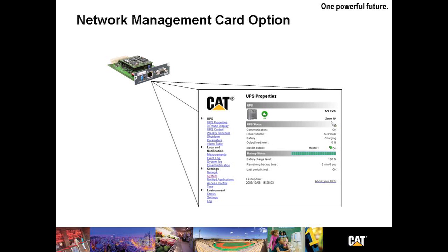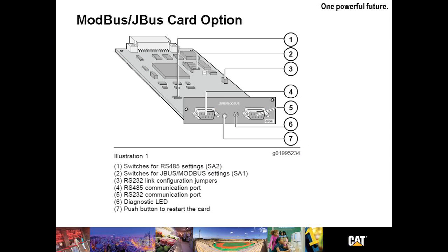The network communication card allows the user to directly connect the UPS to a computer network. The card simultaneously operates as a web server and an SNMP agent. Remote connections are made using an ordinary internet browser or a network management system station. This network management card provides email and text notifications as well. The Modbus Jbus card option provides the different UPS conditions and measurements in Jbus or Modbus protocols. The Jbus hexadecimal or Modbus RTU protocols are used in slave mode. The system provides a communication channel with an RS-485 or RS-232 interface.